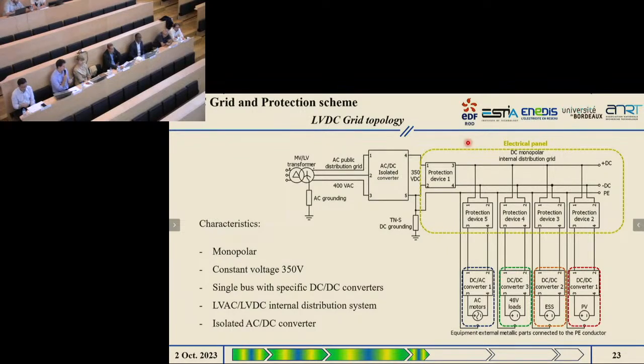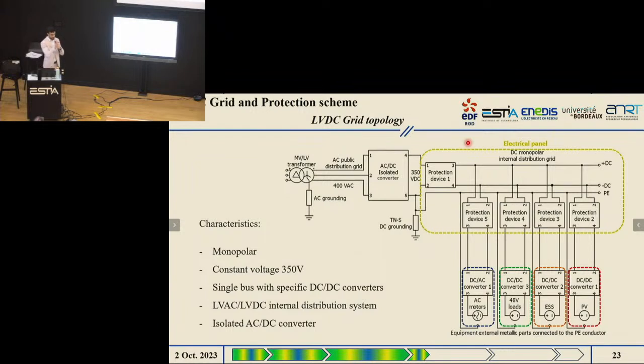So we decided to put two fuses because from the side of protection regarding pole-to-pole faults, we only needed one. But as we are considering a TNS grounding system, and analyzing pole-to-ground faults, considering that it behaves exactly like a short circuit and a pole-to-pole fault, it would be interesting to protect both poles from pole-to-ground instead of only pole-to-pole. To protect pole-to-pole, only one is necessary. To protect from pole-to-ground, maybe two are necessary if there is a residual voltage between the negative pole and the TNS grounding system.